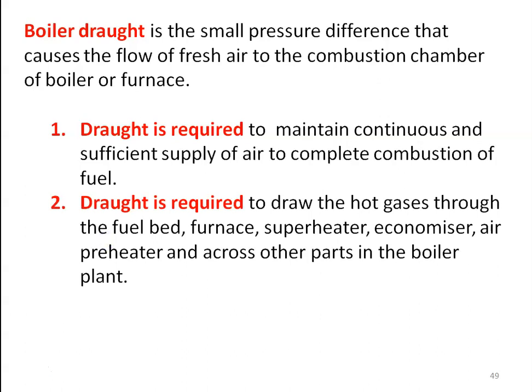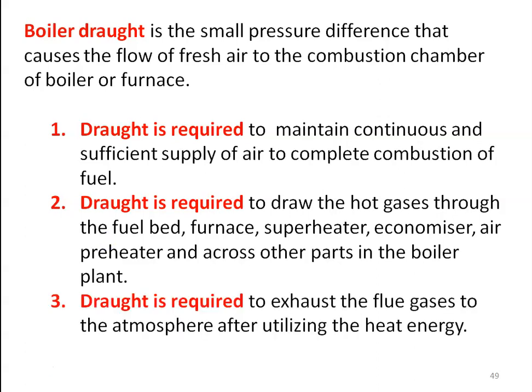The draught is required to draw the hot gases through the fuel bed, furnace, superheater, economizer, air preheater, and across other parts of the boiler plant. The draught is also required to exhaust the flue gases to the atmosphere after utilizing the heat energy. So the draught is the pressure difference between atmospheric air and the hot gases, required for these three functions: to maintain continuous flow of air for complete combustion, to flow hot gases through various boiler components, and to exhaust flue gases to the atmosphere.